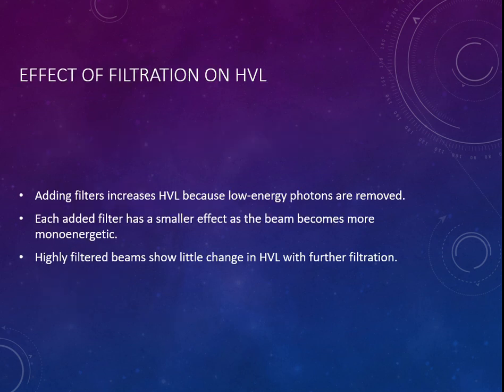Slide 5, Effect of filtration. Adding filters to the X-ray tube removes low-energy photons that don't contribute to image formation, but increase patient dose. As filtration increases, HVL also increases, making the beam harder. However, once most of the low-energy photons are removed, additional filters make very little difference.